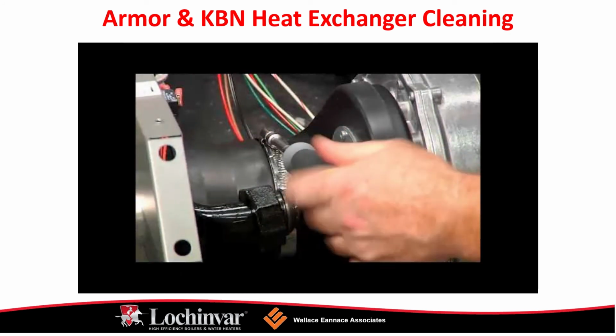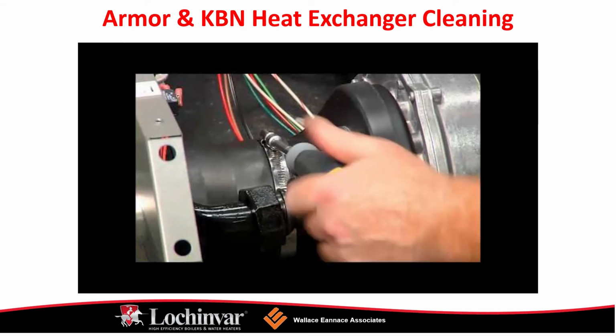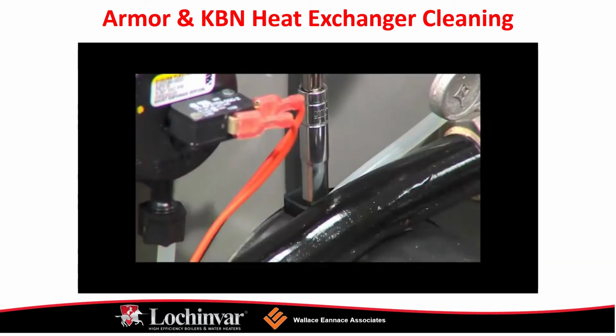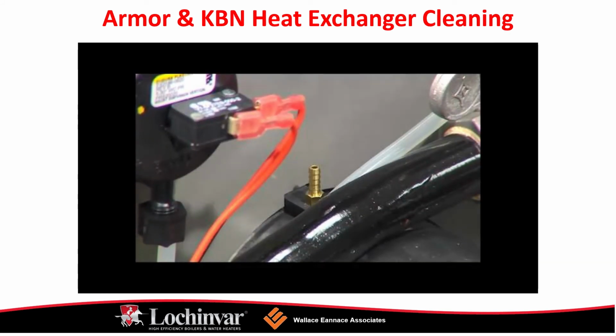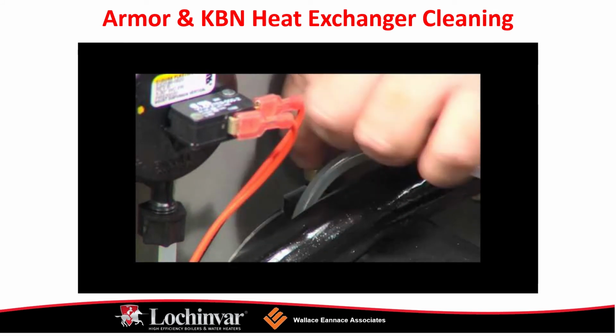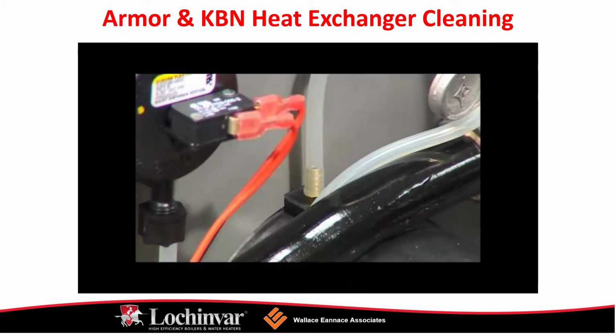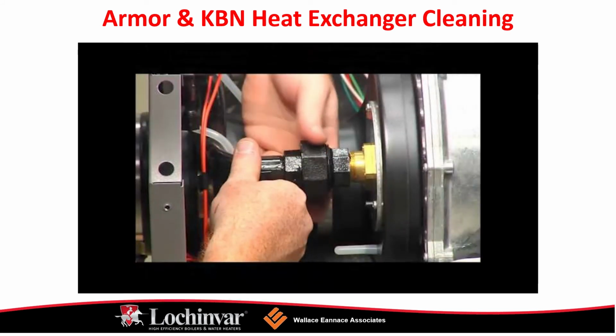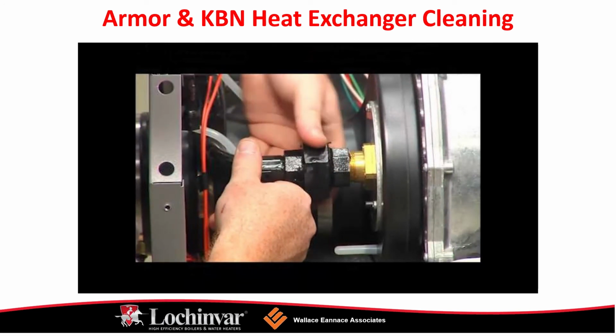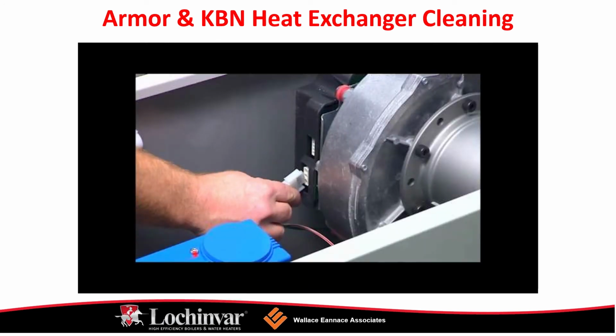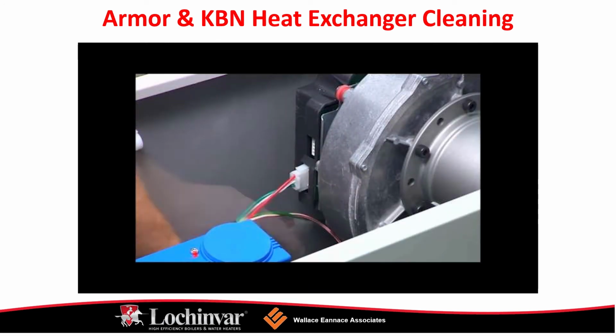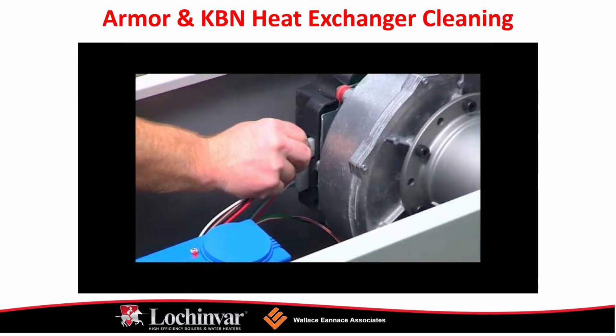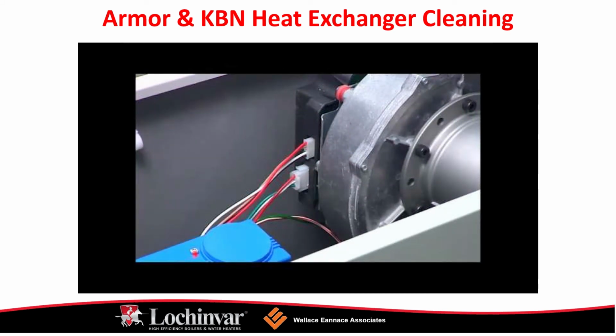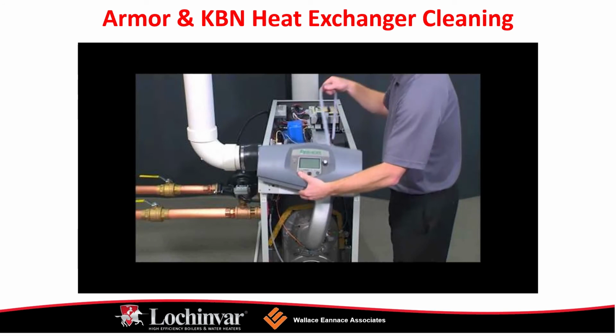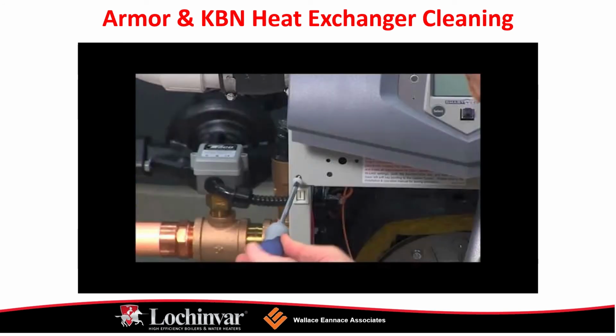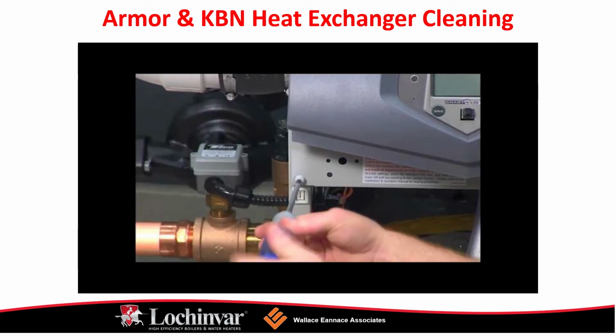Inspect the coils for any soot deposits or dirt accumulation. Use a vacuum cleaner to remove any loose debris from the heat exchanger coils. Brush the heat exchanger coils using the nylon wheel brush supplied in the optional stainless steel cleaning kit supplied by Lochinvar, or with a stiff bristle brush. Re-vacuum the heat exchanger coils to remove debris.